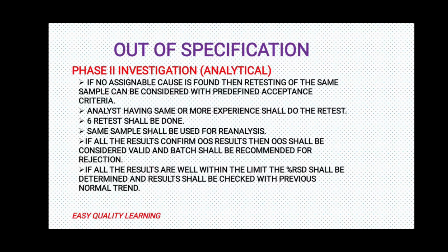If all the results are well within the limit, the percentage RSD shall be determined and the results shall be checked with previous normal trend. So this is one more thing we need to verify, that if all the results are within the specification, then percentage RSD should also be as per normal trend which we are getting earlier.